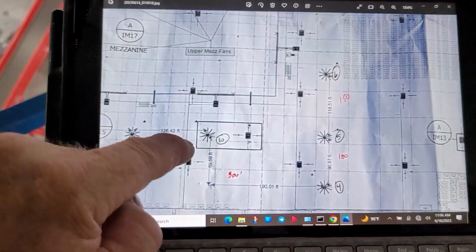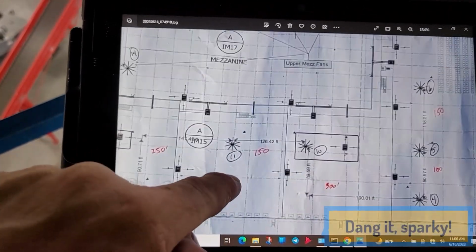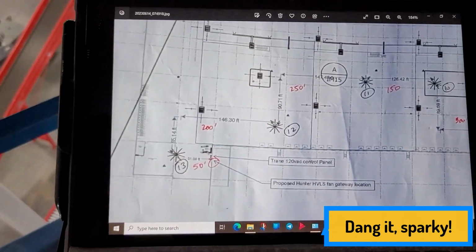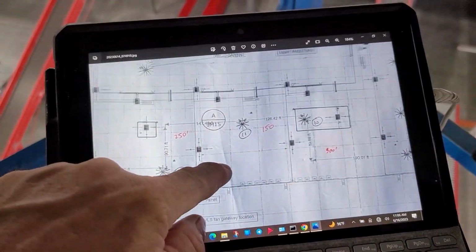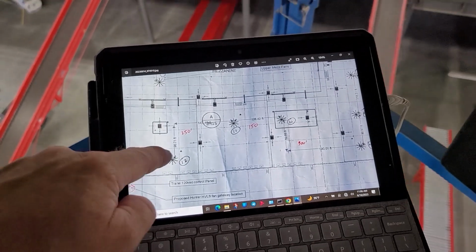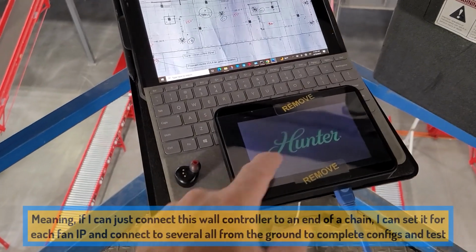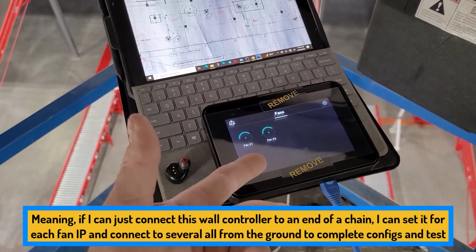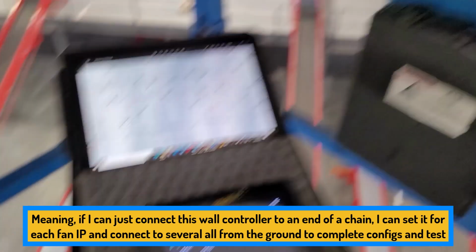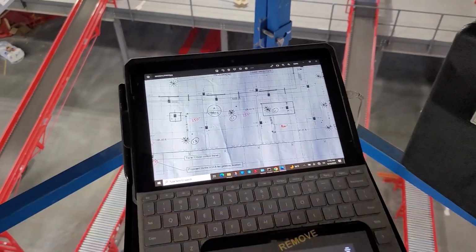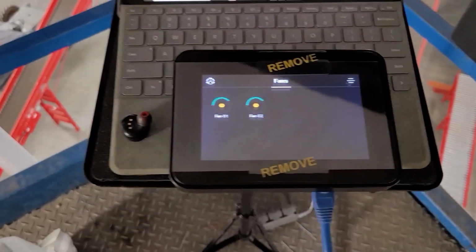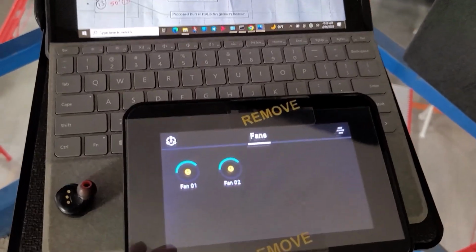Now I'm over here. I've done 4, 5, 6, change the addresses, change on 10, but when I got to number 11, there's no fuses, no power. Now I'm on 12, just change the IP address. Because this one has no fuses, no power, I cannot use this daisy chain all the way back to use this device once. It takes like 2, 3, 4 minutes to boot up, so you have to do that at each fan. It takes forever, but now I'm going to be kind of stuck and breaking it up like that because I don't have the power fan in the middle of the chain.